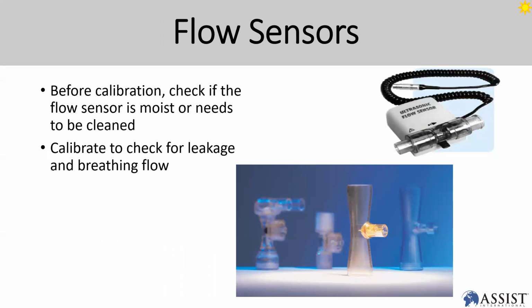Flow sensor is another important component in your ventilator. So basically, you need to calibrate them as well, to make sure the flow is working properly. You can compare the results with the ventilator analyzer. So you calibrate, check whether the flow circuit is clean, and if there is moisture, you need to clean the moisture. Be careful, because sometimes too much moisture, the flow sensor is going to fail.